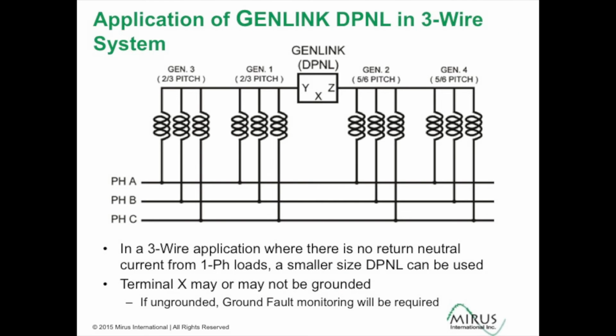This slide shows an ungrounded system application. Here we have 2 generators that have a similar 2/3 pitch, and then another 2 generators that are 5/6 pitch. So we can combine the generators that have the same pitches and feed that combined neutral into the DPNL, and also feed the neutral from the other combination of generators with the same pitch into the DPNL. We don't need to ground this. If it's an ungrounded system, then you have to have ground fault monitoring and all the things associated with ungrounded systems.